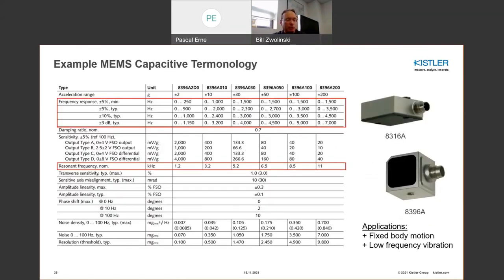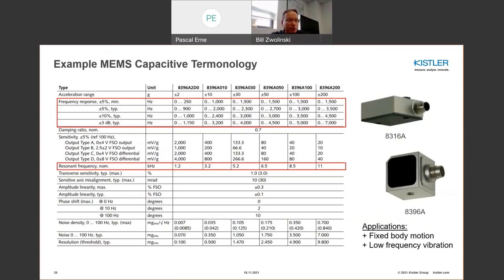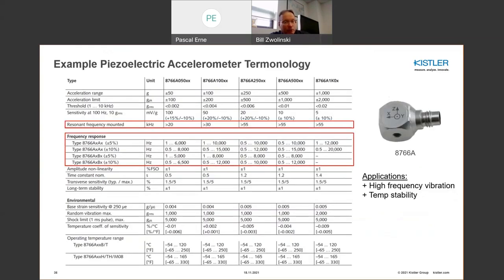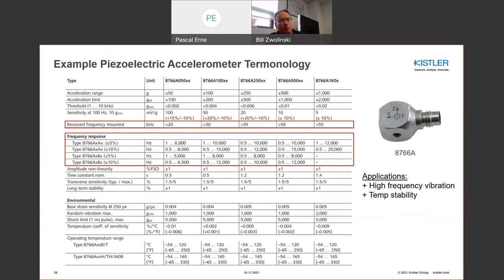Piezoelectric accelerometers are more commonly used, but for fixed-body rigid body motion, MEMS capacitive accelerometers are also used because they provide both high frequency and static frequency response — allowing you to measure any low-frequency rigid body motion of the air structure. With piezoelectrics, you see high resonant frequencies and bandwidths up to 20 kHz at 10%, which gives a real chance to measure high RPM prop shafts with multiple blades, allowing measurement of resonant frequencies and harmonics of that operation.